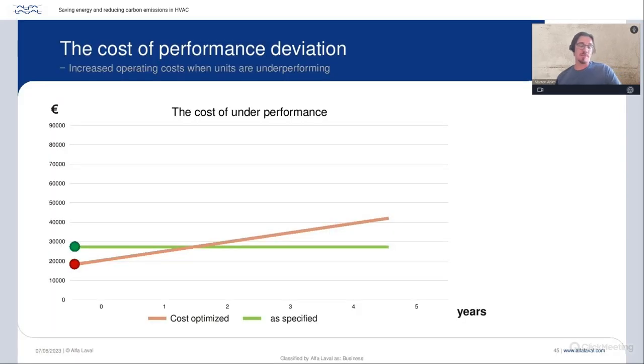I've been doing a lot of this analysis, and with the electricity costs we've had, nowadays it's even higher. So the payback time for the additional investment would actually be shorter. But typically we end up with a payback of getting the right design of something like 1 to 2 years. That is where the undersized or cost-optimized unit will start to cost more money, thanks to the additional yearly operating cost. So it makes sense to actually get the performance you have asked for.